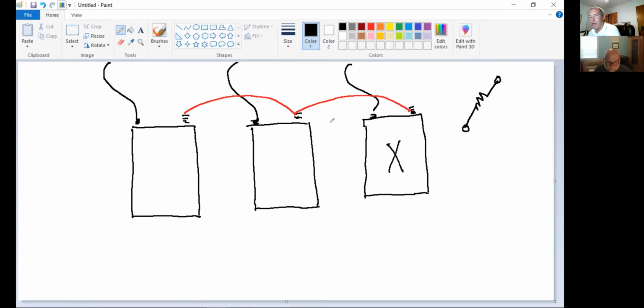It has to go up. It's going to try to raise itself as quickly as possible to be able to compensate for the lost load, because there's no path to follow. I don't have it attached to ground, okay? If the voltage raises up and spikes in these transformers that are still energized, it's going to go to the customer. We don't want that to happen.